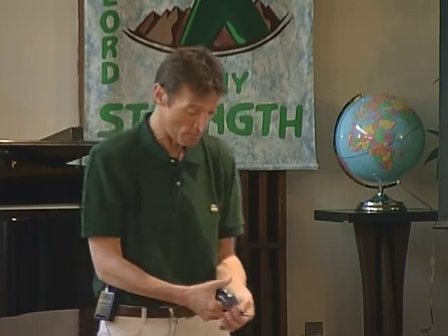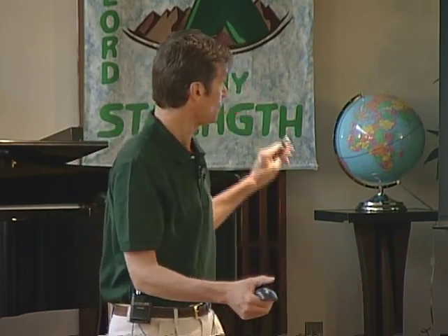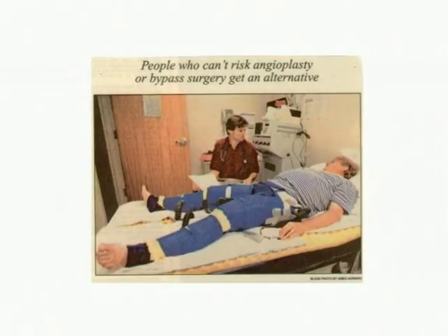Well, with external counterpulsation, and first of all, we've been doing this 10 years. Here's a picture of us when we first started. This is me without any gray in my hair. The patient lies on a padded bed. We wrap large pneumatic cuffs, large blood pressure cuffs, over the calf, the thigh, and the pelvic region. And we inflate and deflate with compressed air. We hook you up to an EKG on your finger. You wear a plethysmogram to give us a non-invasive capillary waveform.